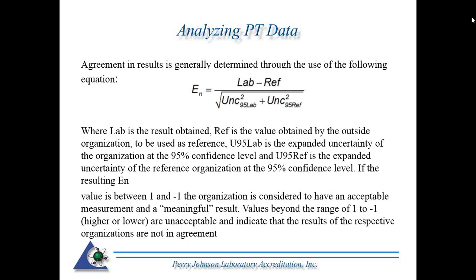U95 is the expanded uncertainty, K equals 2, or the 95% confidence level of the organization. And U95 reference is the expanded uncertainty of the reference organization at the 95% confidence level in the resultant E-normal equation. So the reference, that's the other participating lab. Of course, your lab would report where it says lab, that's your value. Uncertainty at 95% of the lab, that would be your value.